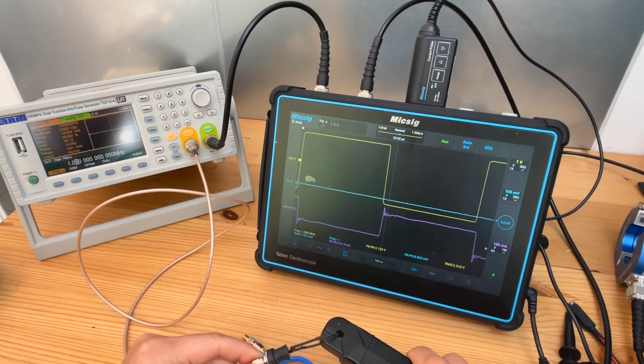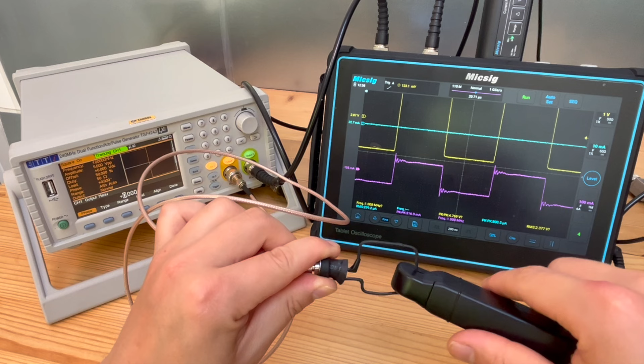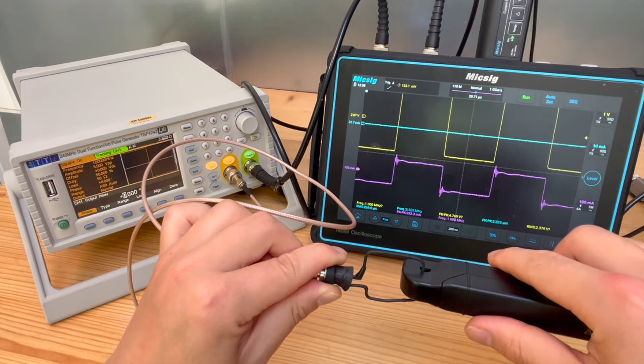So one thing I can do is move this current probe, and you can see the ringing and overshoot start to change as I move it alongside the conductor. So you can see as I move the current probe, the overshoot and ringing behave differently. This gives me the feeling that perhaps it's due to the measurement rather than the waveform itself.